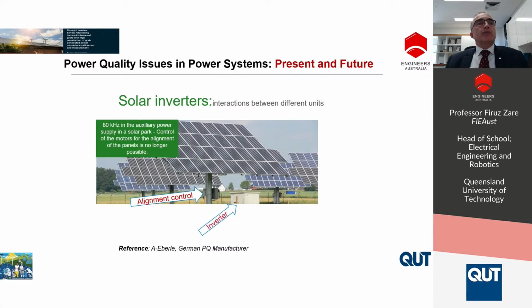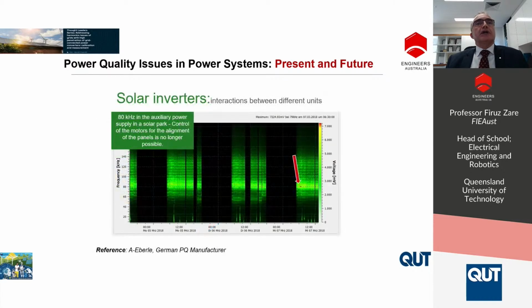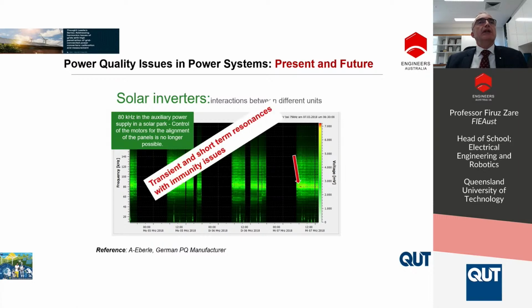This is the other example being reported by A-Eberle, and they reported that the alignment control, which is based on a power electronic motor drive, was connected at more or less the same point of common coupling as the solar inverters, and they realized that the control system was affected because of this high frequency. If you see that red area, that is the high frequency content of the harmonics that affected the control system. So when you have different high frequency power electronic systems connected together, apart from harmonics generated by the device propagating to the network, they can interact with each other, and depending on their internal impedances, current harmonics can circulate through another device, affecting its control system. So again, this is transient and short-term resonances with immunity issues.